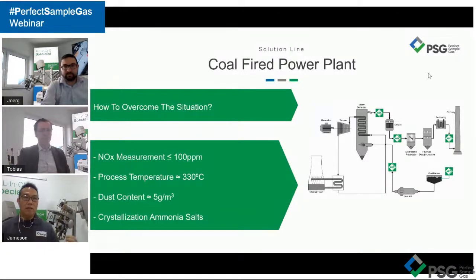Yeah, so big questions about ammonia. Many people buy ammonia probes without understanding why they choose the ammonia probe. There are many suppliers, but as far as application is concerned, as a system integrator, as a stakeholder, we must understand a few things. We know that the temperature is proportional to the NOx concentration, and we reduce the amount of NOx by injecting ammonia, with a catalyst. And then we have to overcome process temperature of above 330 degrees. Generally, it's 360 degrees. Why is it so high? Because of the presence of SO3, the very high acid dew point of SO3. That is a contributor to the ammonium sulfate, which we call in short the ammonia salt.